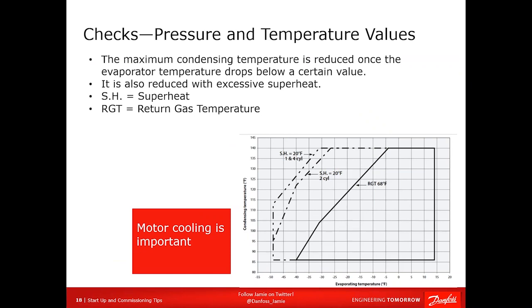So once again, here we have RGT, return gas temperature. This compressor cannot operate at any condition if the return gas temperature is above 68 degrees. Why? Because there is no way to cool that compressor properly. So notice how small the application envelope is compared to 20 degrees. So as your superheat goes up, you start to move those dotted lines on the left side of the diagram further and further over to the right and down. So instead of operating at 140 degree condensing, you're going to be operating at 125 or 120. So keep that in mind.